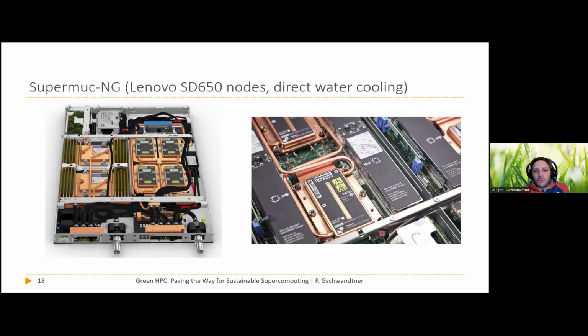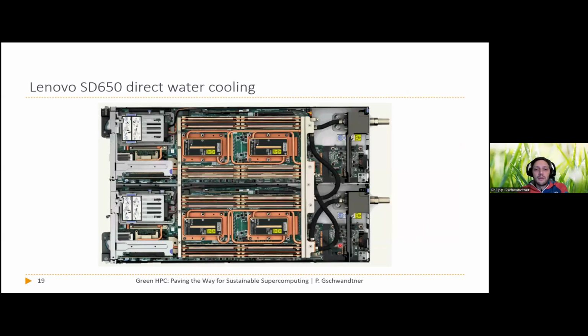This shows how tight tolerances are when it comes to cooling, because doing cooling wrong doesn't necessarily mean the system breaks, but it may run less energy efficient. On a large scale, in a system that costs 50 or 100 million euros, for example, that's really an important factor.